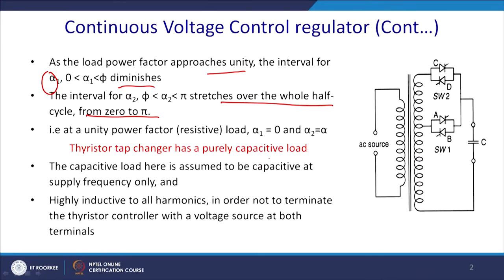Now, let us take another option, if the load is purely capacitive. The thyristor tap changer has a purely capacitive loading. It is quite difficult to analyze because you know that a series capacitor is dangerous. It requires di/dt protection and all those things. But since there is a leakage inductance across it, a series inductance is already inserted. So, you can use it.